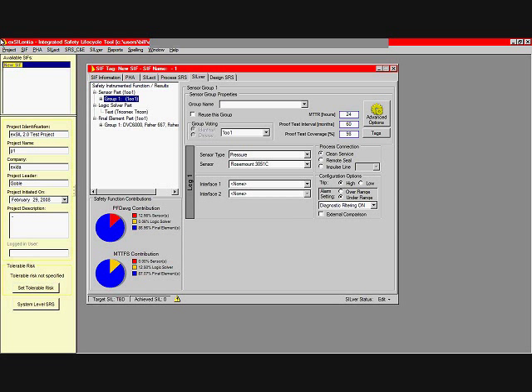So I'm going to pick a Rosemount 3051C, a very popular pressure transmitter. I've got clean service. I do not have a remote seal. I don't have a problem with impulse line plugging. It's a high trip, and I'm setting the diagnostic alarm to under range. But I'm going to turn on diagnostic filtering.